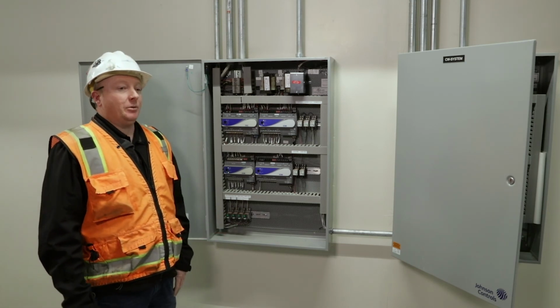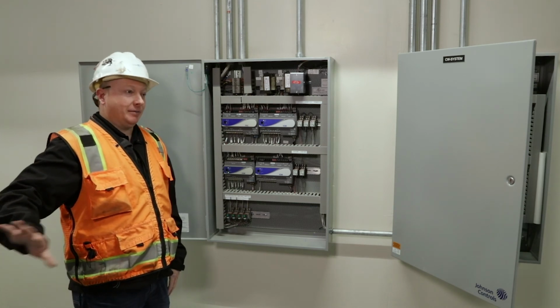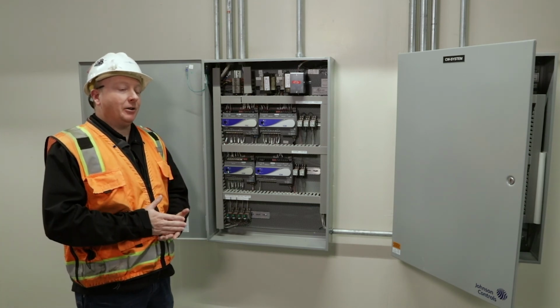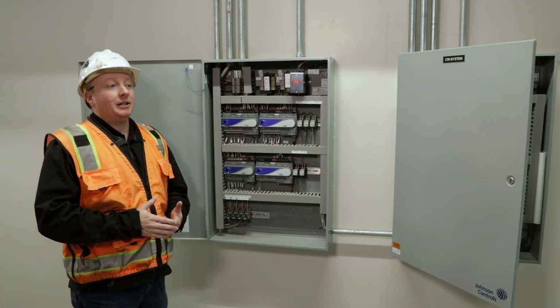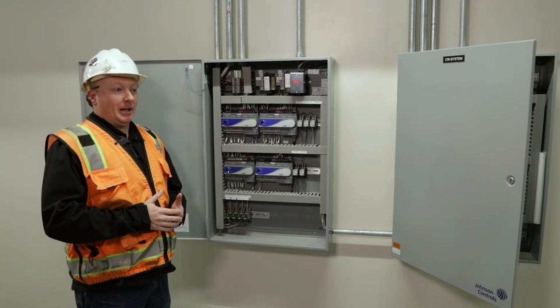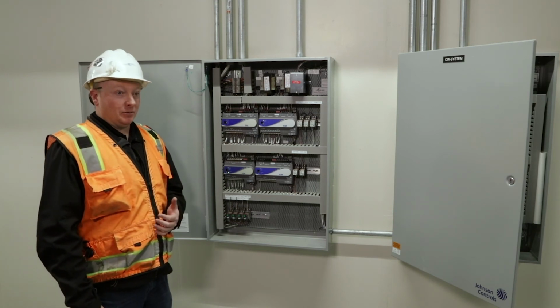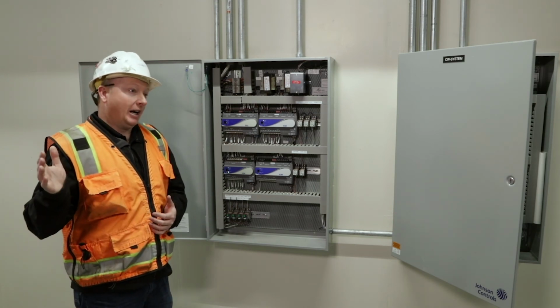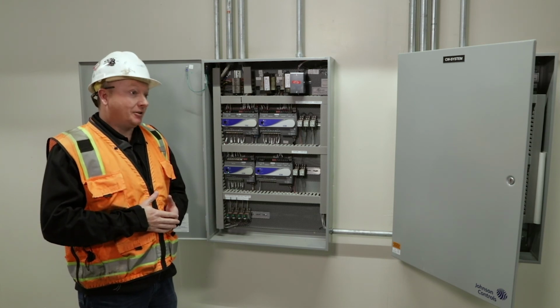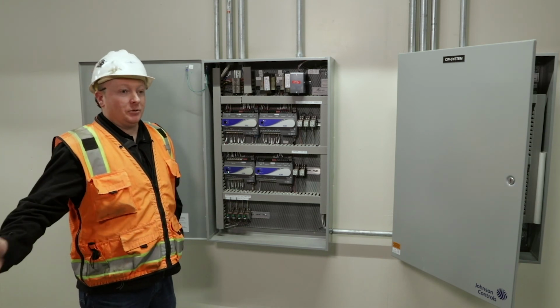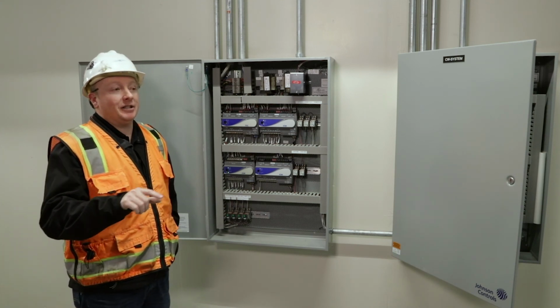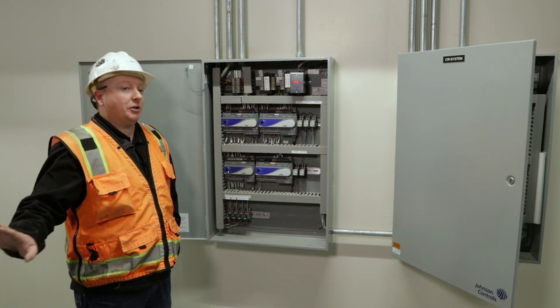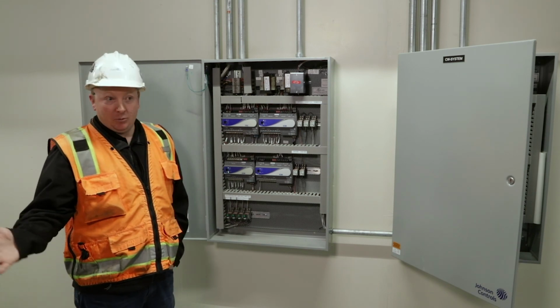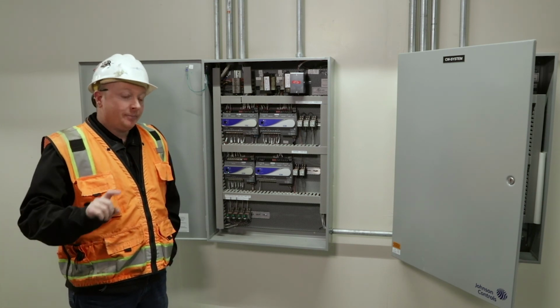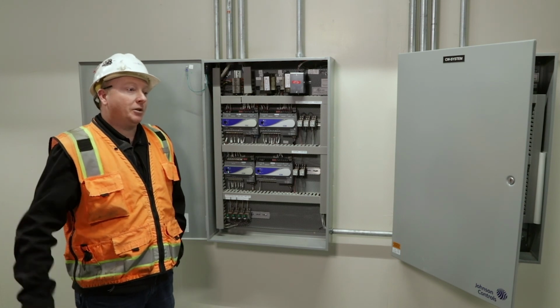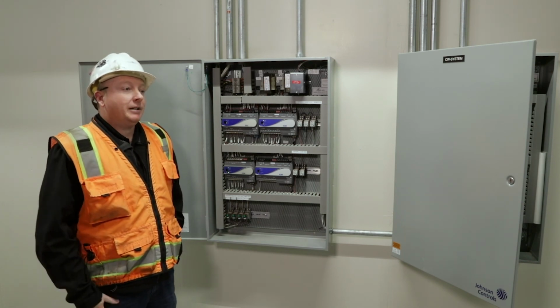So if you want one chiller to run and not the other, there's a couple ways you can do it. If you want to keep the staging control there, you can just manually override that runtime value on the chiller and you can put it to some really high number, and that will always make it the lag chiller. There's also a maintenance switch for each one in the BMS where you can basically just take it out of service and say, I don't want chiller 2 to run at all because we're either doing maintenance on it or we don't need it, whatever. You can just disable that point and it'll just ignore chiller 2 and just keep going to chiller 1.